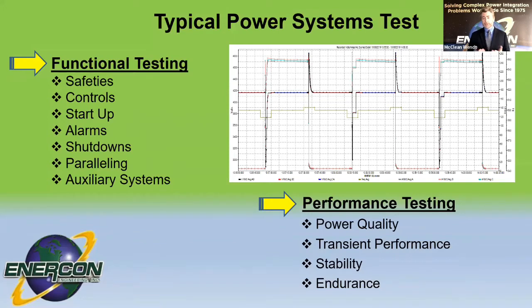And so we'll simulate various different alarms that we can do safely. Some we may do by changing a set point to verify that a controller is capable of that alarm. And then other situations we'll simulate by actually creating that condition. So for a low coolant level, we may end up draining off some of the coolant from the expansion tanks of the radiator until that alarm trips, and we'll get a warning. And then if there's a shutdown, we'll drain it down to that shutdown, make sure that the engine transitions to a safe state.